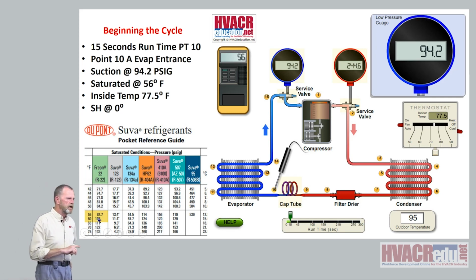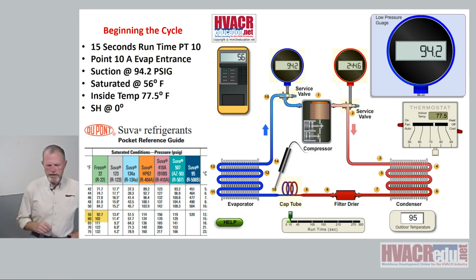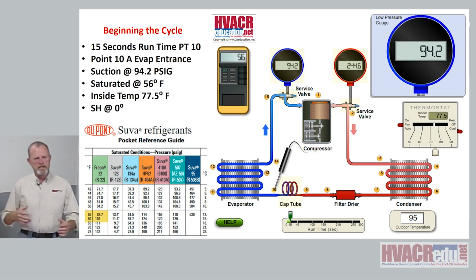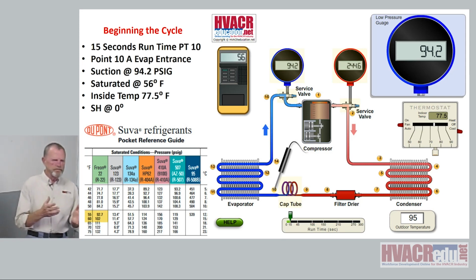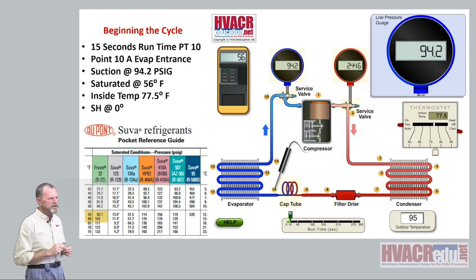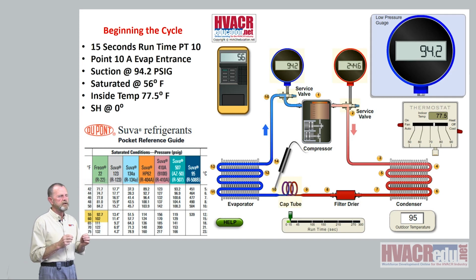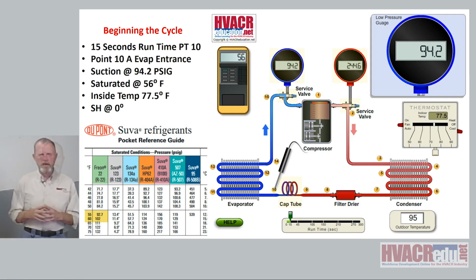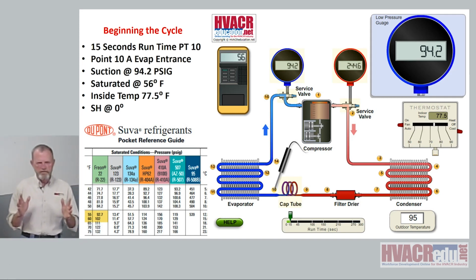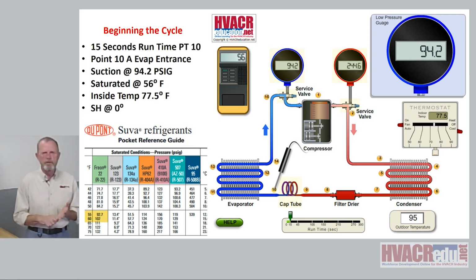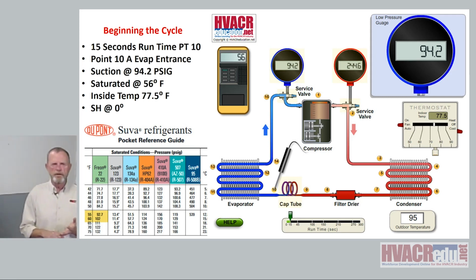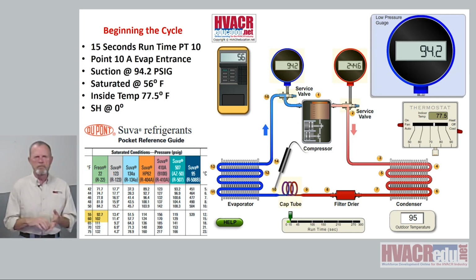One thing to say about pressure temperature charts: not all charts are created the same. As I was putting this together, I had an Alco pressure temperature chart on the desk with me, and I was comparing it to the Suva DuPont chart. I was sitting there going, oh geez, they're a little bit off here, a little bit off, they're different, all right? But the important thing to recognize is everything's going to be different. How accurate are your gauges? How often do you adjust and calibrate your gauges? If you don't do that on a regular basis, they're going to be a little bit off.